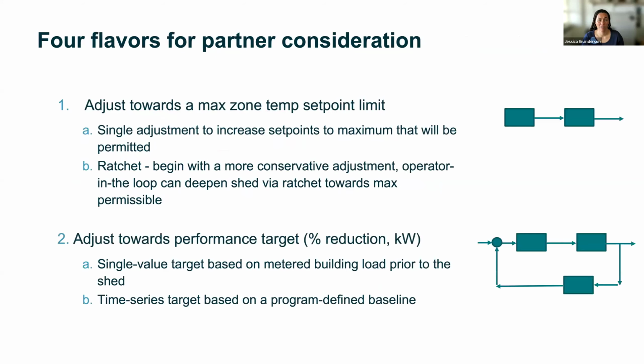Let's talk about that. There are a lot of ways you can do this, and our spec has articulated about four, or two of them, depending on how you want to count. One is that you might define a maximum zone temperature set point, like never will I go above 78 degrees, it's too brutal for my occupants.